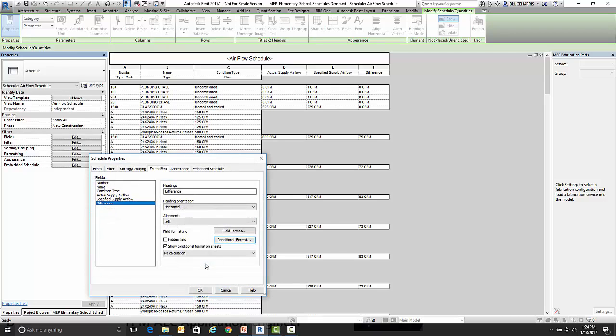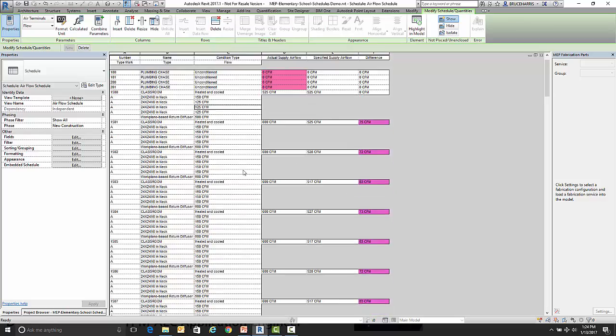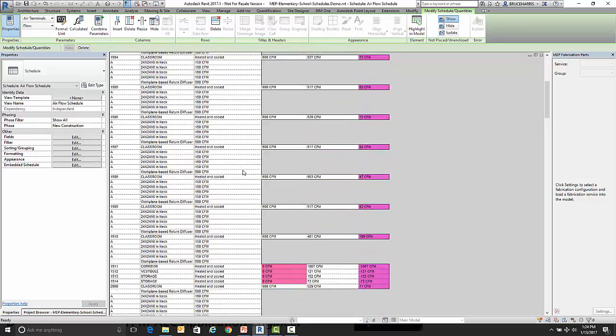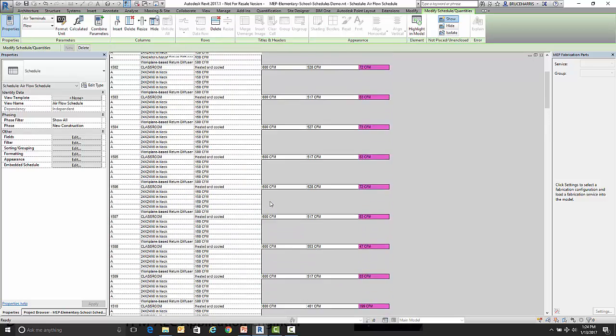So now if my actual air supply is set to zero, I've got a red in there for me to know that I potentially have a problem there. So here I can see right next to it, it's an unconditioned space, so zero is okay. Now further down my list, I have some heated and cooled areas that are at zero CFM. So I know I have a problem there and I need to work on that problem.